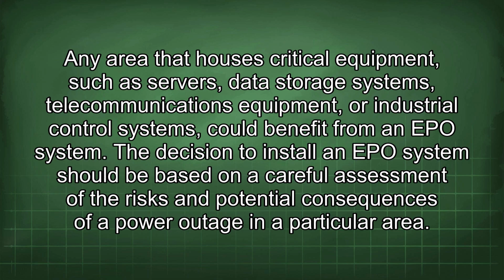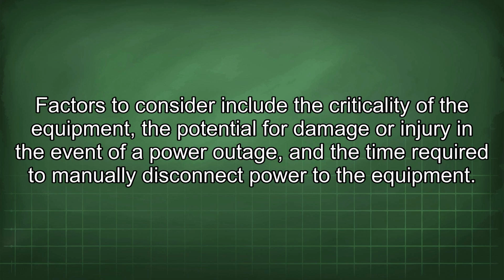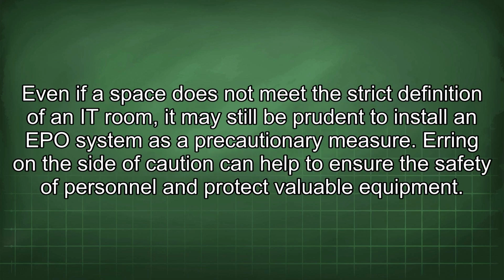The decision to install an EPO system should be based on a careful assessment of the risks and potential consequences of a power outage in a particular area. Factors to consider include the criticality of the equipment, the potential for damage or injury in the event of a power outage, and the time required to manually disconnect power to the equipment. Even if a space does not meet the strict definition of an IT room, it may still be prudent to install an EPO system as a precautionary measure. Erring on the side of caution can help to ensure the safety of personnel and protect valuable equipment.